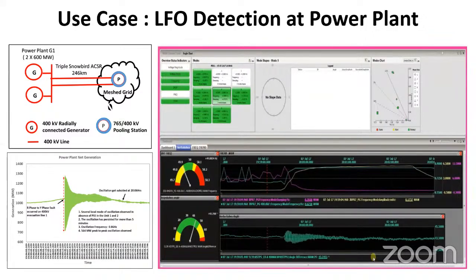So coming back to the question of this 2012 blackout. The actual issue, if you look in terms of an electrical engineer: the protection part of that particular line, which was heavily loaded. At that time, there was a zone 3 issue, where it was encroaching into the zone 3 region, and due to the load kind of component, the resistive reach component that is coming, it encroached into the zone 3 part. Due to that, the protection operated. Those kinds of things were not generally envisaged. And that led to the tripping of that particular line, and there were some additional forced outages.